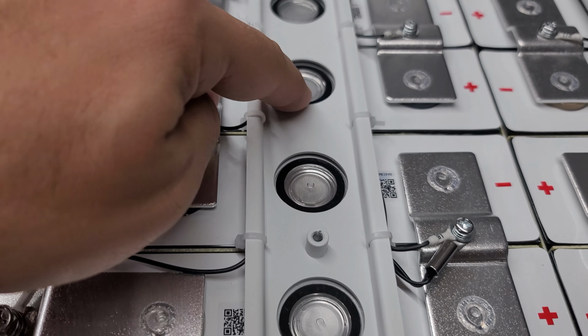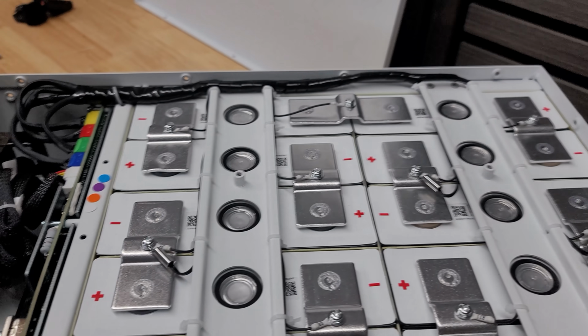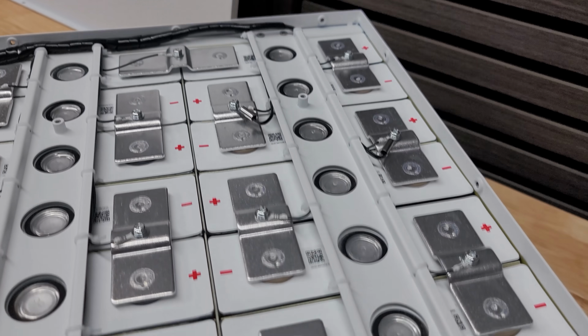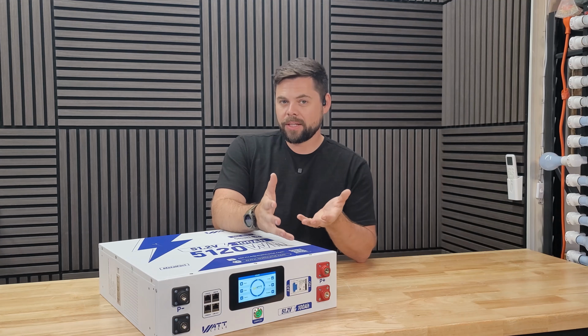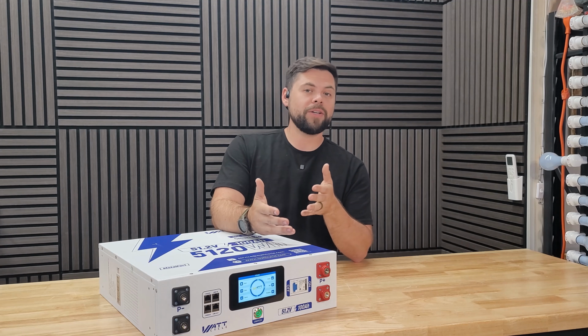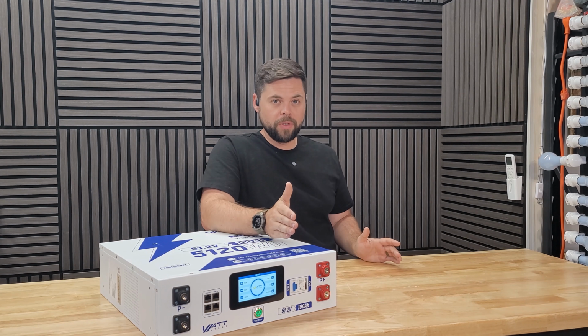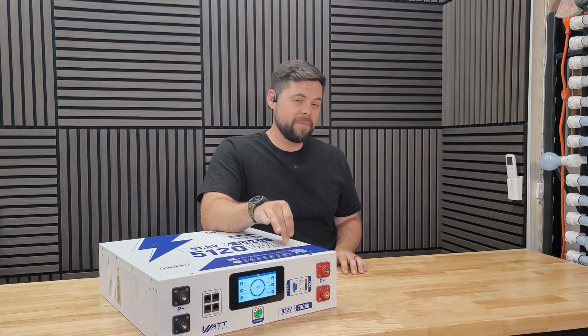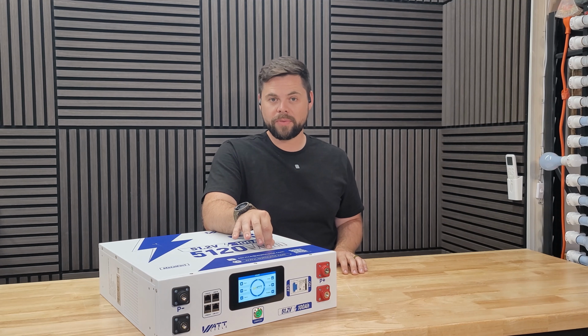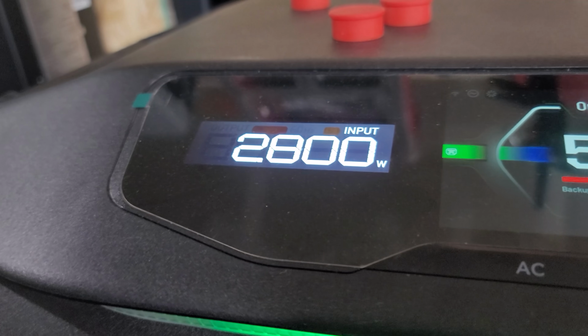Underneath the hood, I did not find a fire extinguisher or fire suppressant of any kind inside. It's not necessarily required depending on your application, but it is preferred, because this does not have the UL 1973 certification, which is required in order to use a battery in conjunction with the grid.